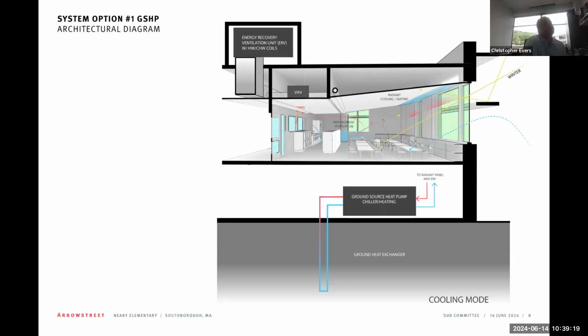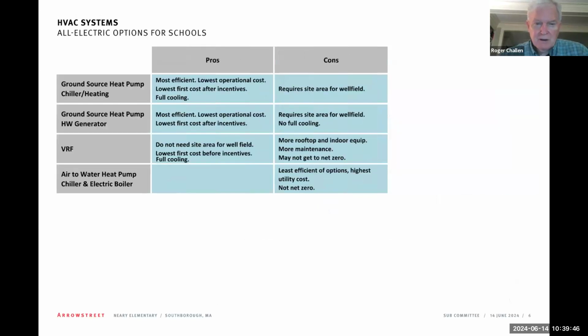I think so, but radiant panels, right? GGD would need to confirm that. Okay, because that makes sense. You're already bringing the pipe into the classroom for the radiant panels. You can do the VAVs with the hot water reheat as well. I'm 99% sure that it is, but they could answer that. So Kate, could you go back to the summary of four diagrams?